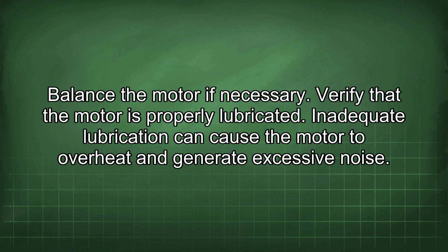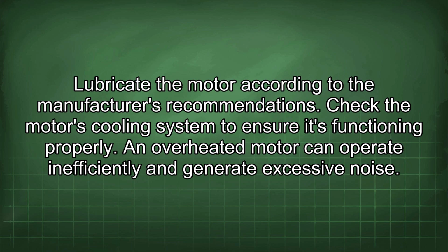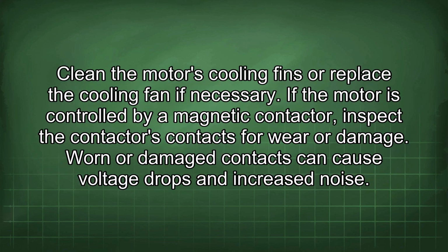Verify that the motor is properly lubricated. Inadequate lubrication can cause the motor to overheat and generate excessive noise. Lubricate the motor according to the manufacturer's recommendations. Check the motor's cooling system to ensure it's functioning properly. An overheated motor can operate inefficiently and generate excessive noise. Clean the motor's cooling fins or replace the cooling fan if necessary.